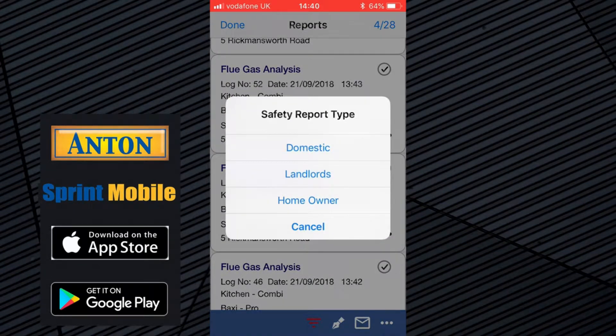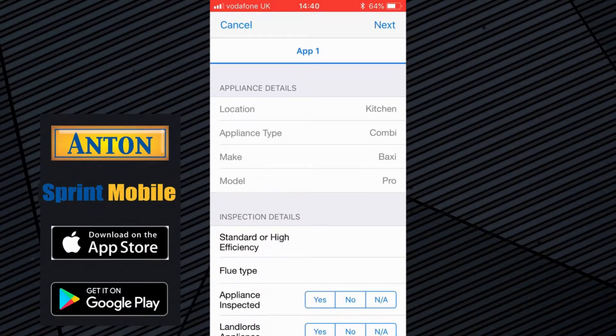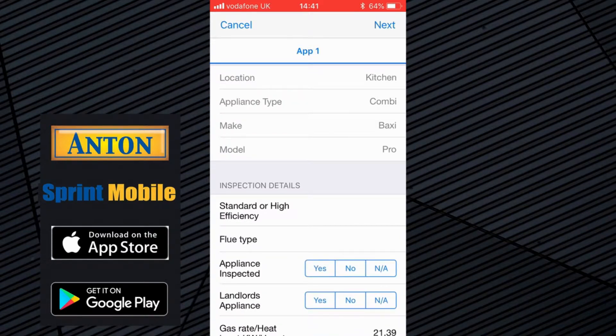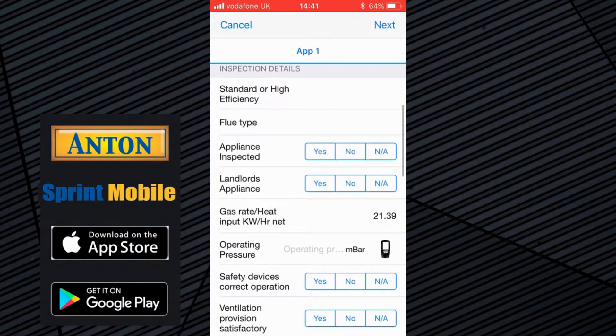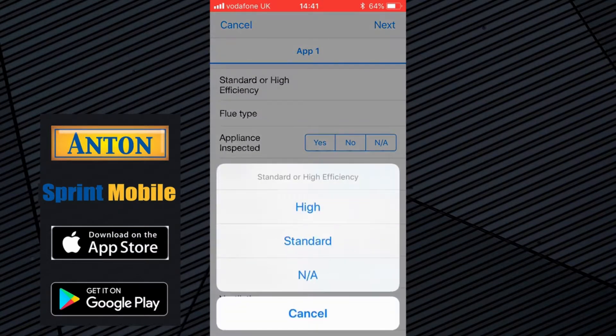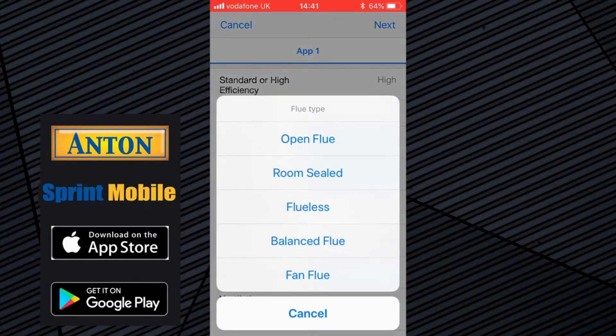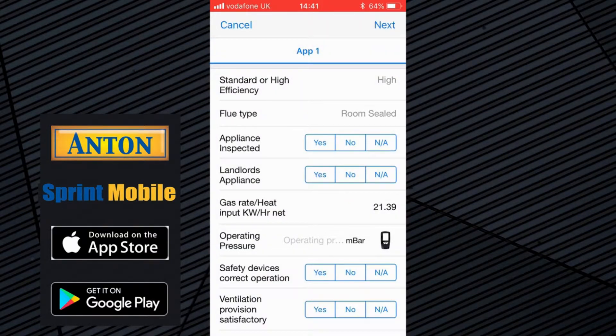This is a fictitious landlord we're working on here, so I'm going to select the landlord option. There's only one appliance. Obviously if you link reports for more than one appliance — maybe the cooker or whatever else is in the property — you'd have two tabs at the top and two lots of data to fill in. Because we've linked it to that property, it's already taken in the location, the appliance type, the make and model of the unit. It's a high efficiency boiler with a room sealed flue — just like filling out your traditional landlord gas safety record, or CP12 as some people call it.